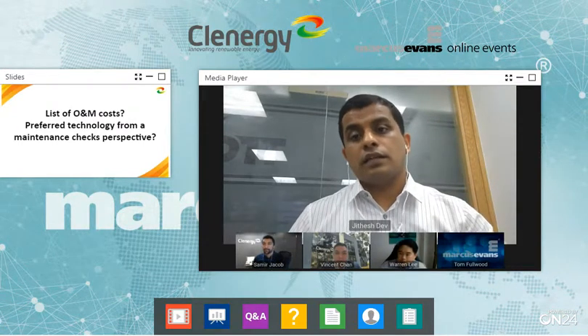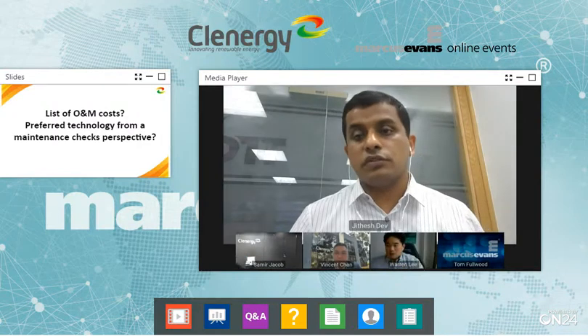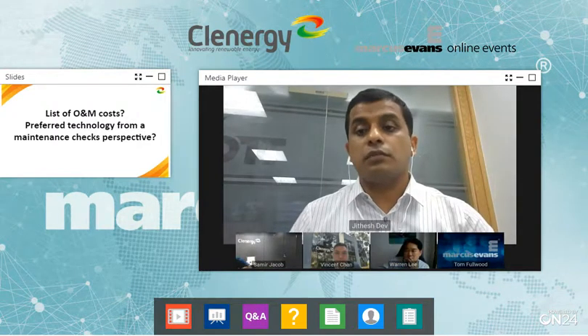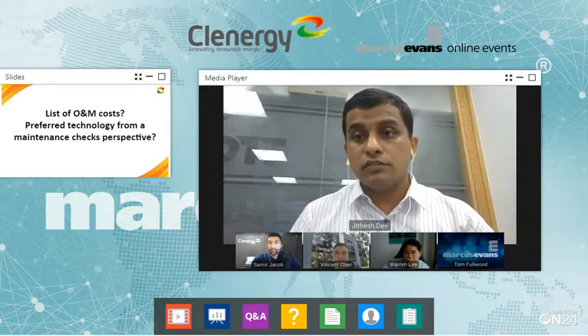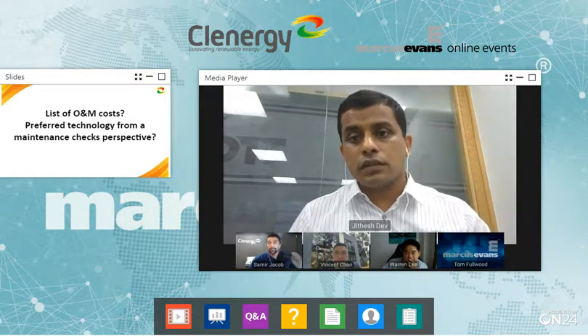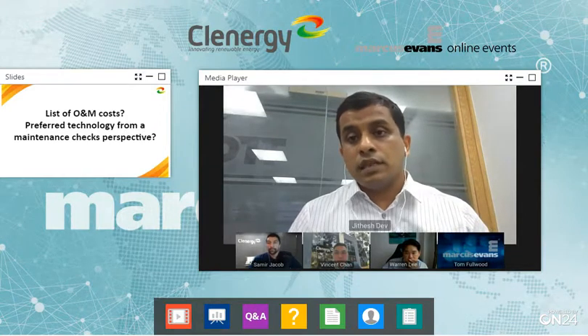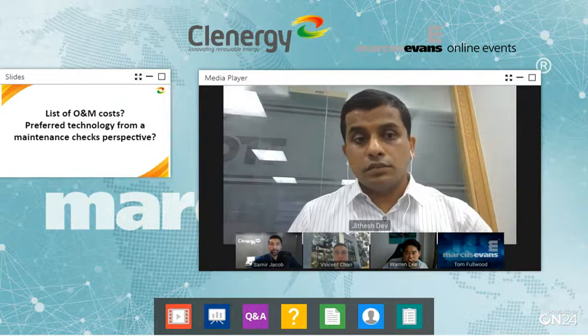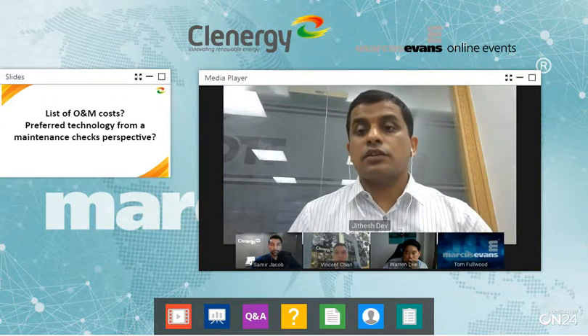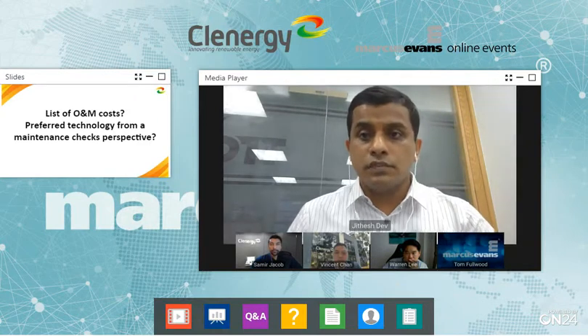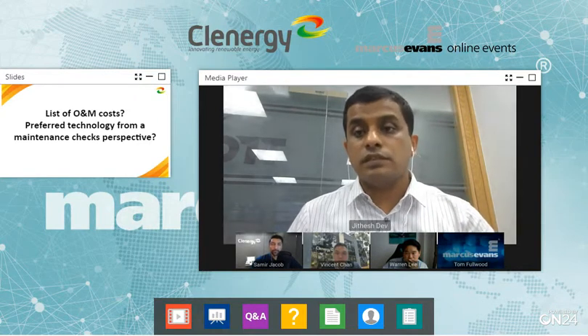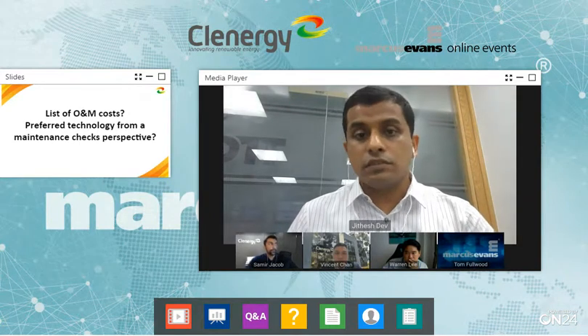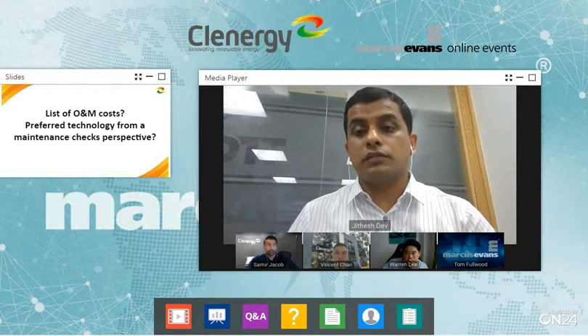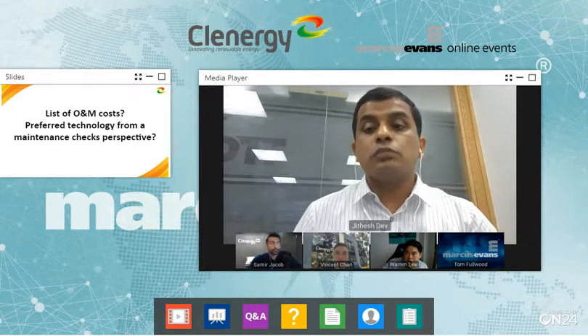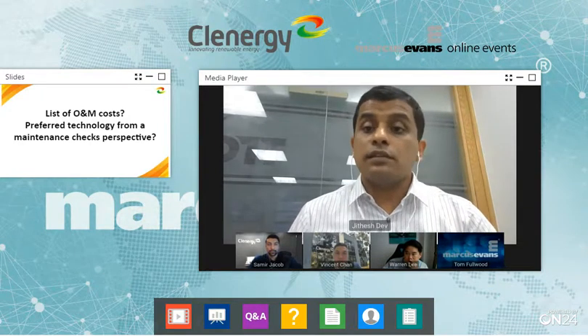You need a checklist for each step of the maintenance process for different components, such as modules, structure, inverter, string combiner box, and all critical components. If that's in place and your site team is doing plant maintenance correctly, tracked by ERP software where you can monitor how preventive maintenance is happening, you'll see a performance increment from the plant due to these activities, improving the availability of the plant to greater than 99%.